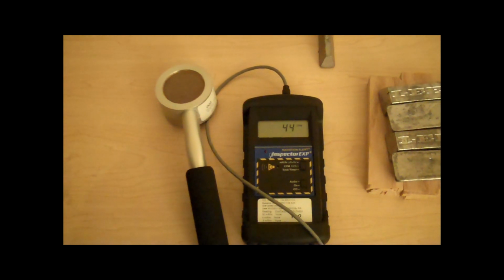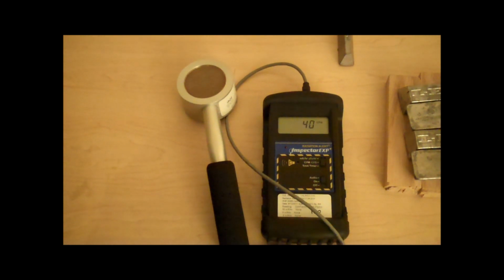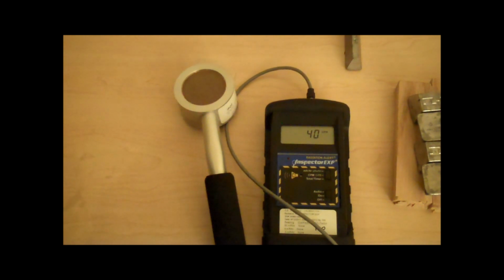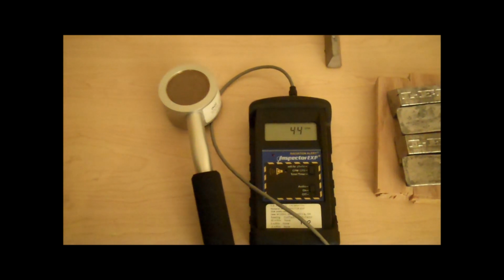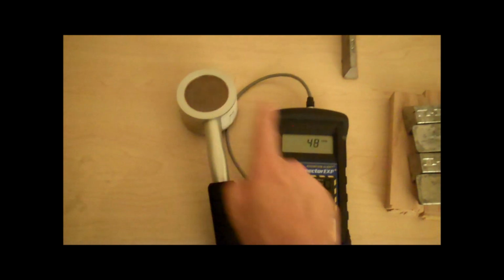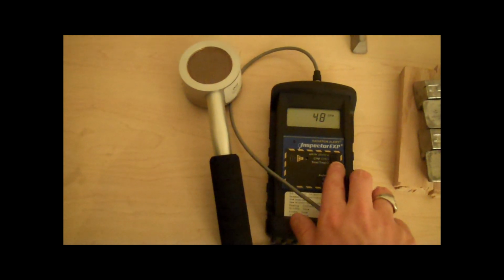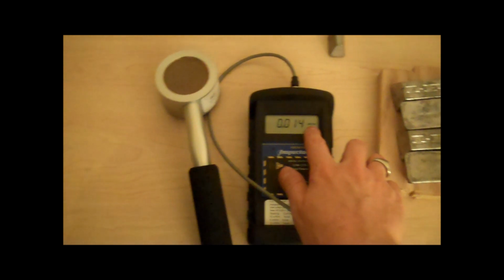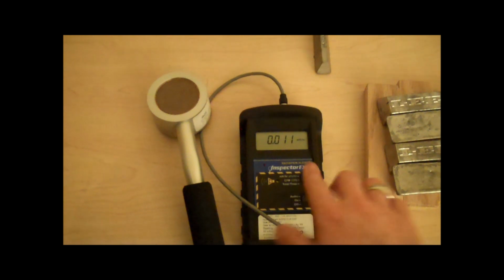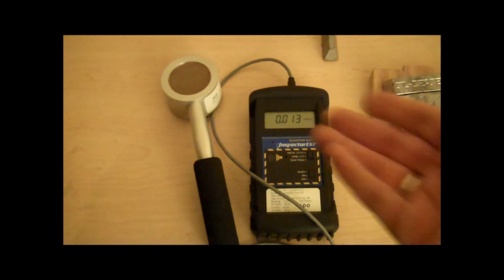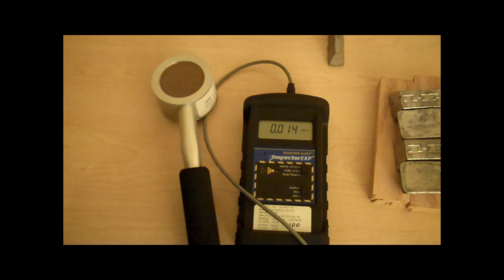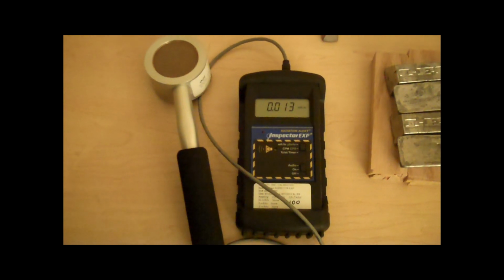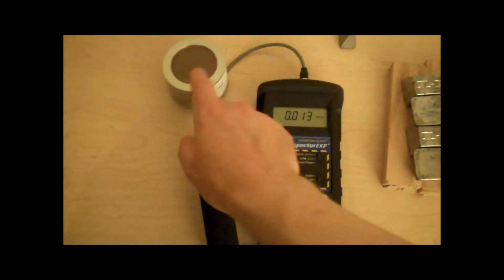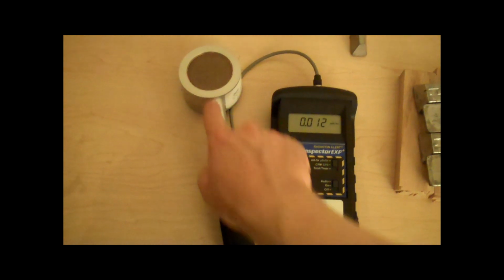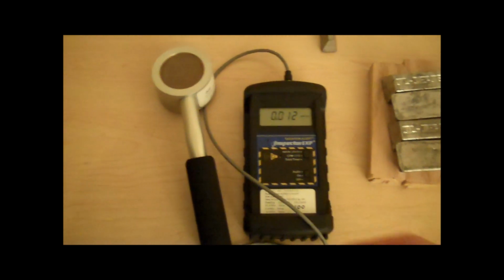The drawback to this device, besides its inefficiency at detecting gammas, meaning that many gamma waves can move straight through the detector without actually being picked up, with only a very small fraction actually being seen, is that for each successful detection, there is one and only one count. Any energy that it attempts to show you, such as this reading of milliroentgens per hour, which is an explanation of how much energy is being conveyed to you, they're only approximations. They are not very accurate, because this device does not actually know the true amount of energy that strikes this, only what that energy would be if it was exactly what this was calibrated with.